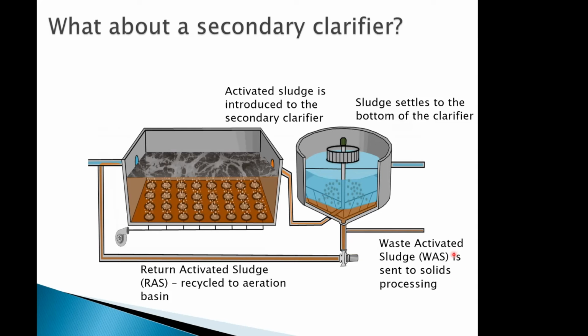Keep in mind also that our waste activated sludge is also mostly organic, mostly biodegradable, because it is bacterial cells, right? It's the mixed liquor bacteria that we have wasted now. And so similar to the primary sludge, this sludge has a lot of energy bound up in it, and we can take advantage of that in a process like anaerobic digestion, where we degrade that biology into its constituent parts, generating methane gas, which we can then use to power a cogen engine, for example, and offset our power costs.